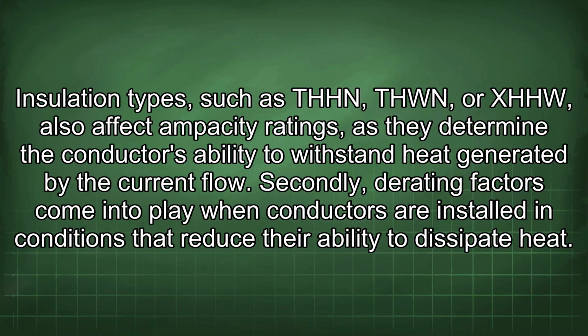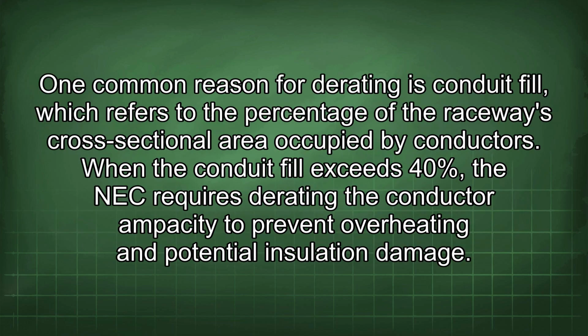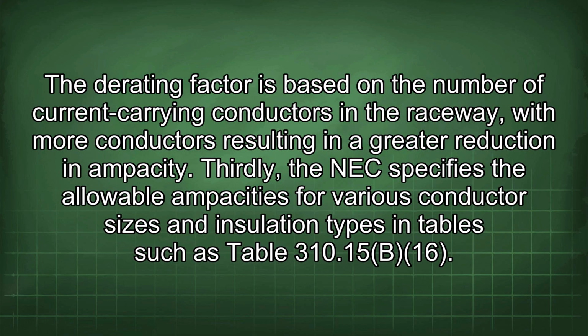Secondly, derating factors come into play when conductors are installed in conditions that reduce their ability to dissipate heat. One common reason for derating is conduit fill, which refers to the percentage of the raceway's cross-sectional area occupied by conductors. When the conduit fill exceeds 40%, the NEC requires derating the conductor ampacity to prevent overheating and potential insulation damage. The derating factor is based on the number of current carrying conductors in the raceway, with more conductors resulting in a greater reduction in ampacity.